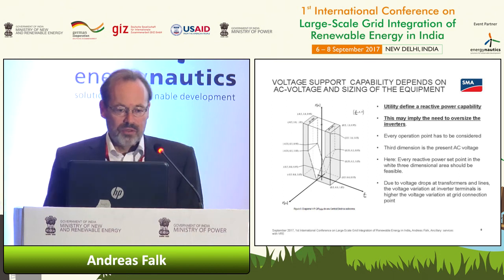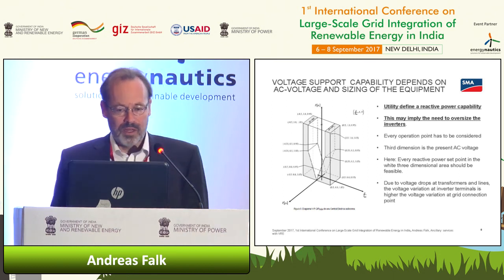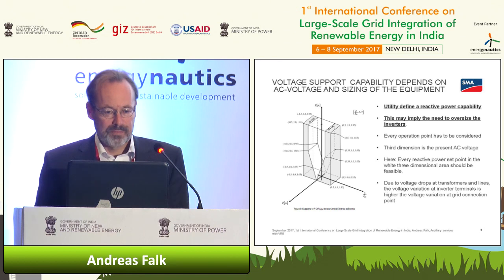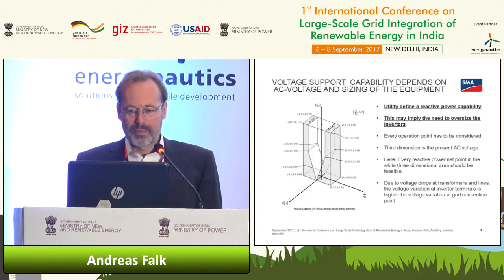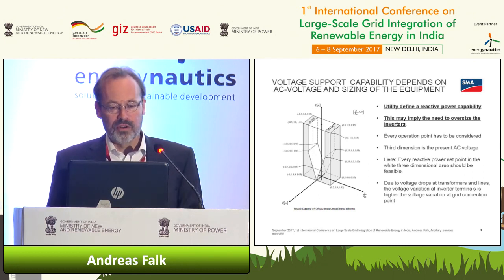Next, I would like to talk about the reactive power capability of a power plant. Normally, the utility defines a reactive power capability. This may imply the need to oversize the inverters themselves or the number of inverters.